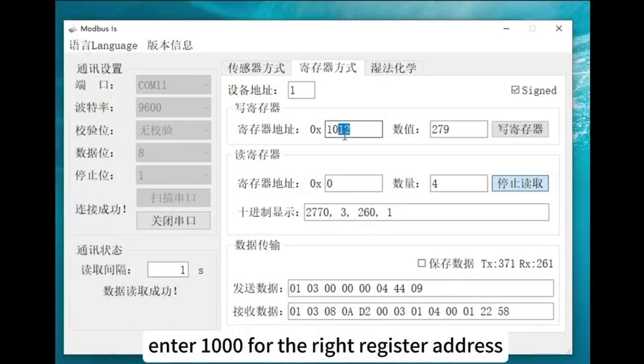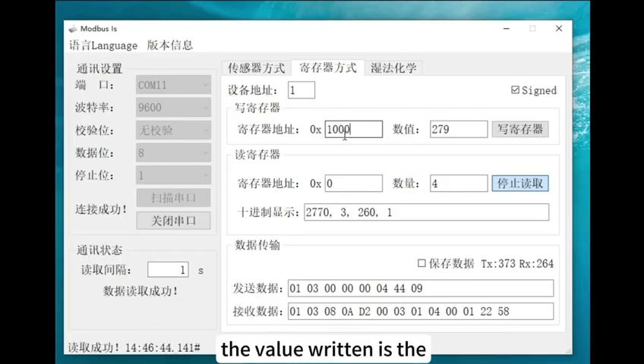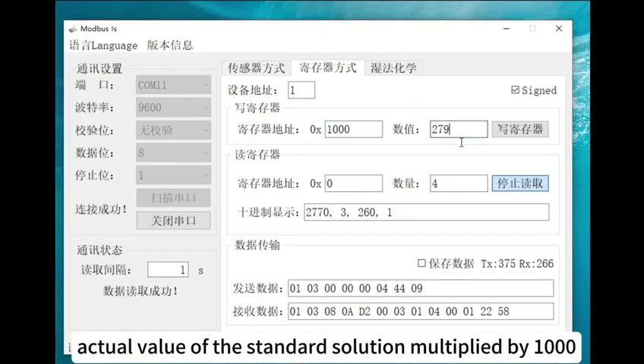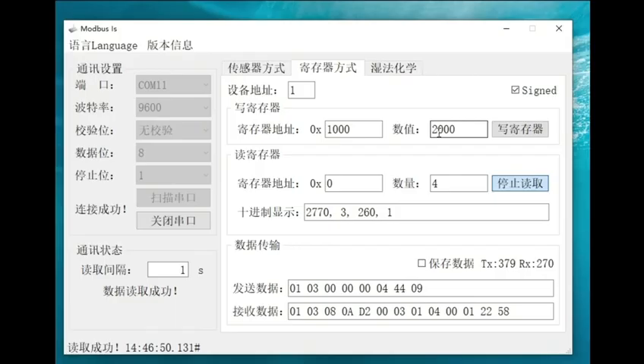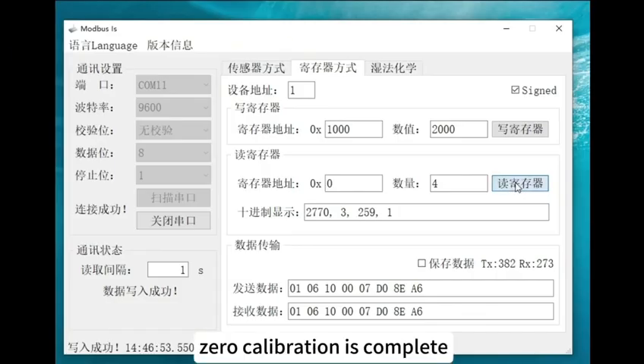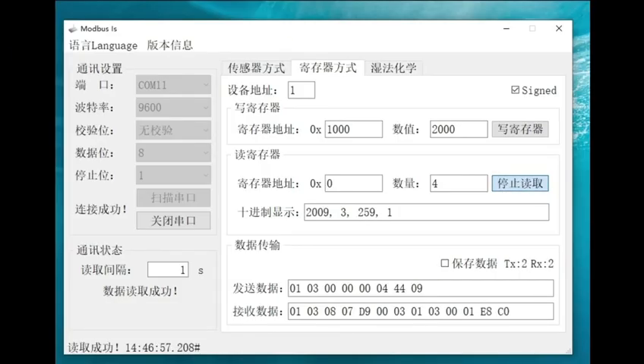Enter 1000 for the write register address. The value written is the actual value of the standard solution multiplied by 1000. Click Write Register. Read the register again. Zero calibration is complete.